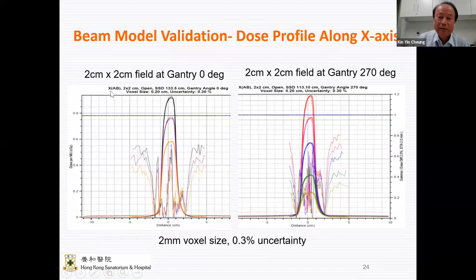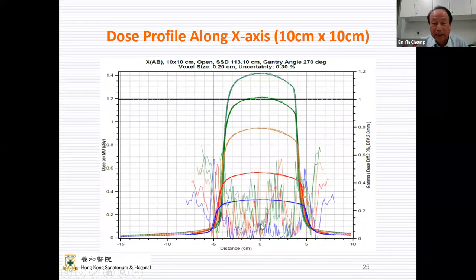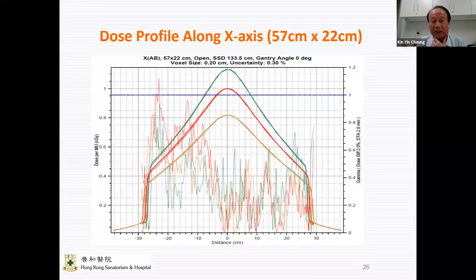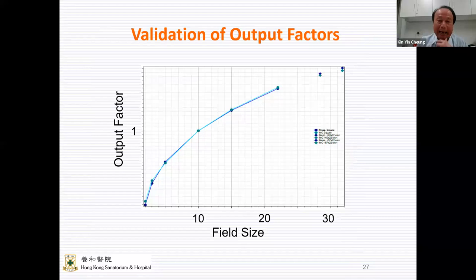And for the profile, on the left is 2x2 cm, 0 degree gantry. On the right is the same field size at 270 degree gantry, and they match pretty well. And this is a profile of 10x10 at 270 degree, just some examples. And a large field size, 57x22 for gantry 0. And for the output factor, the line shown in light blue is the computer calculation, and the one shown in dark blue is our measurement data. They agree pretty well.